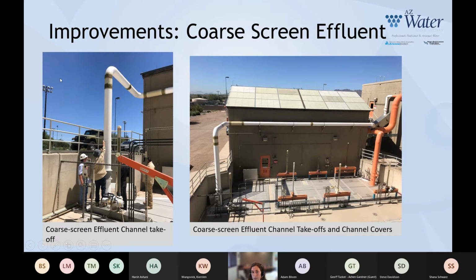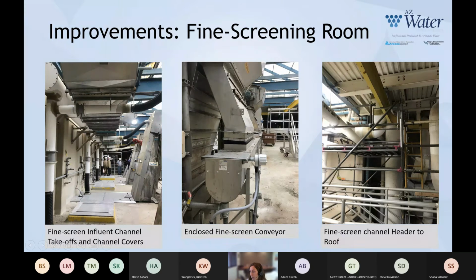some photos. I should note, as we're going through this, all of the existing ductwork is shown in orange. Anything shown in white is the new ductwork that was added. You can see the new channel drops down to the fine screen Influent channels. Reminder, there were channel drops down to the fine screen Influent channels, but we made this header larger so we could collect more airflow from those locations. We also included takeoffs onto the fine screen equipment itself, both with flexible hoses, so you could still access equipment and channels as needed.